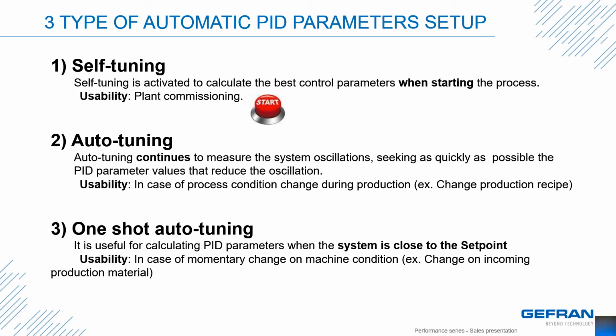Performance series has 3 tuning algorithms to help you determine the optimum PID constants for your process. First is self-tuning. Its suggested use is during the startup or machine commissioning. Then there is one-shot auto-tuning. Use this when you are closer to set point. The unit auto-tunes, sets the PID values, then goes on to control.